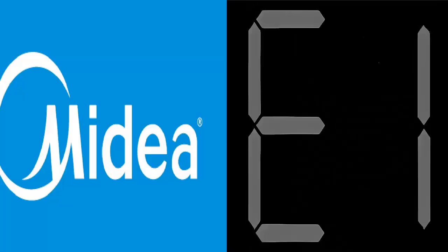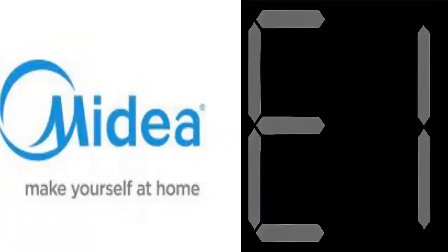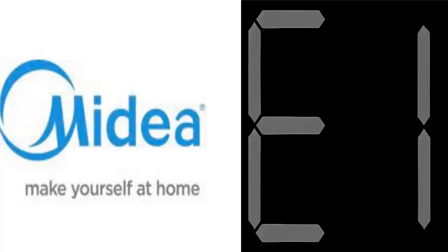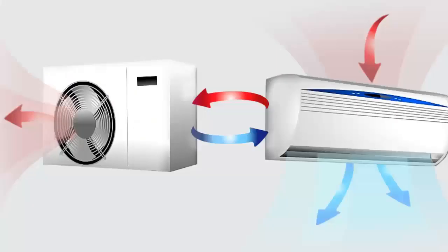In this video, we will explain the meaning of the communication error in Midea inverter air conditioners related to the failure in communication between the indoor and outdoor units. In most units, this error is indicated by the code E1, although it may vary for some models.